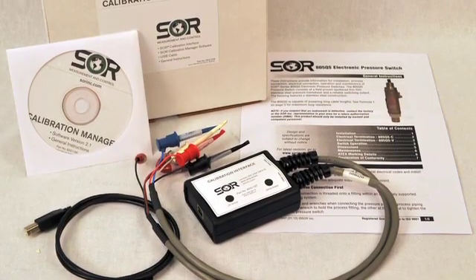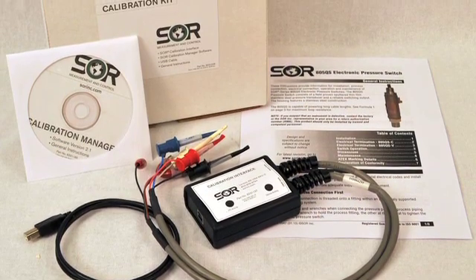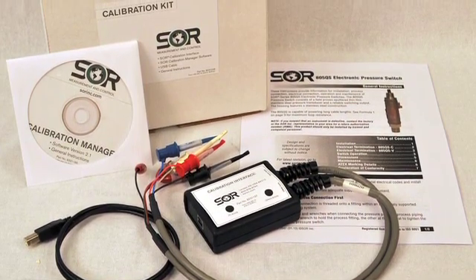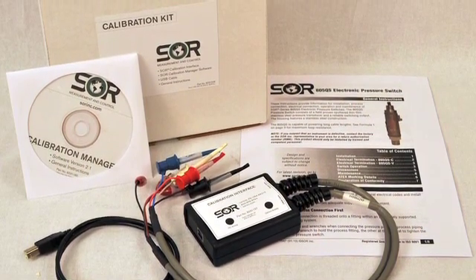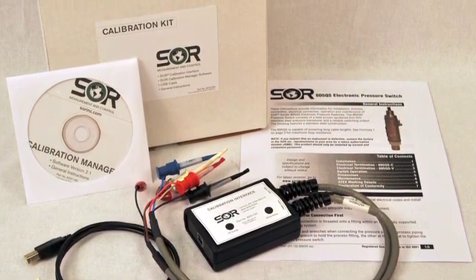The switch set points are set at the factory per the customer's specification. However, both the switch set points and the zero span set points can be adjusted in the field using the SOR optional calibration kit.